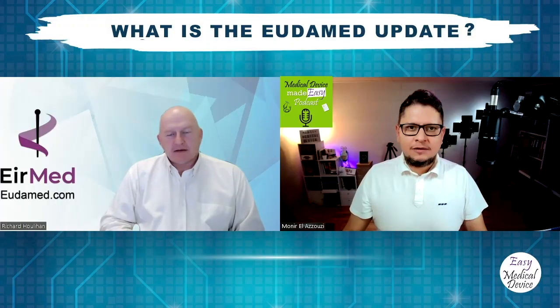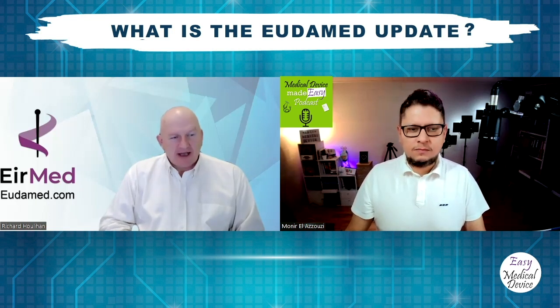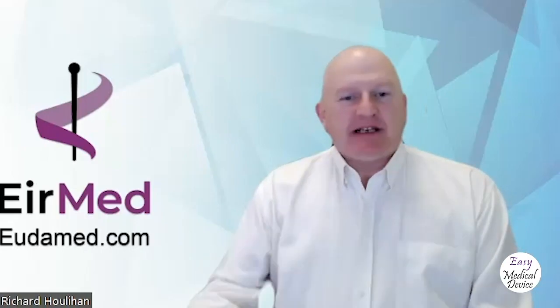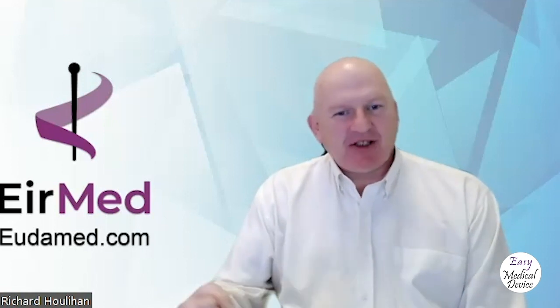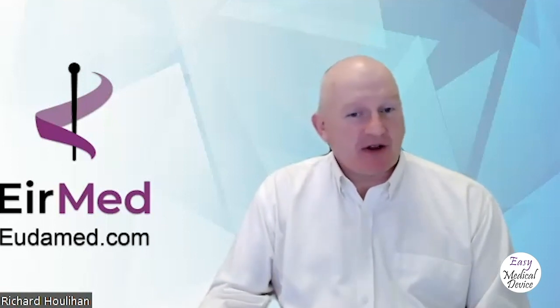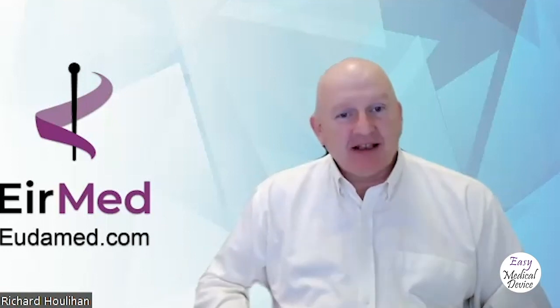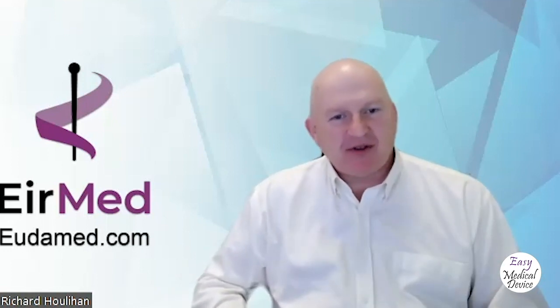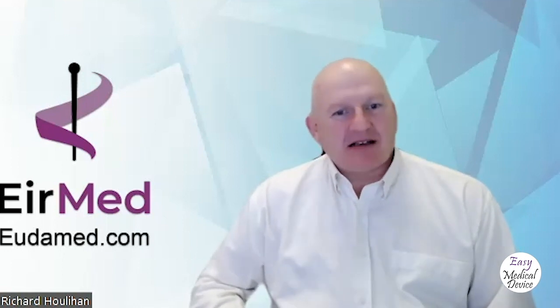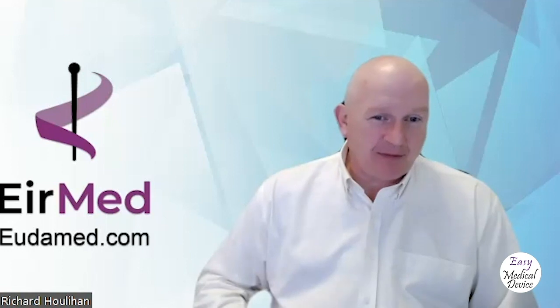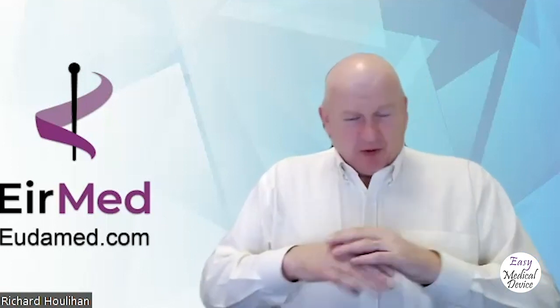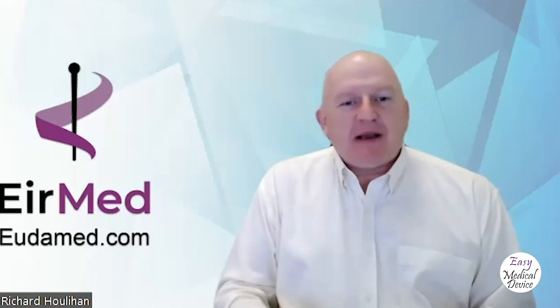We also have a playground that exists for EUDAMED. So what is this playground and how can we use it? Okay, the playground is the Commission's test area. That's the easiest way of putting it. Anybody can register. Same as you could register for production, you can register for the playground. It's the exact same process. You still have to register your company. If you're an authorized rep, you still have to get them to tick the box. The competent authority still has to approve your registration, etc. But once all that's done, you can play with EUDAMED.